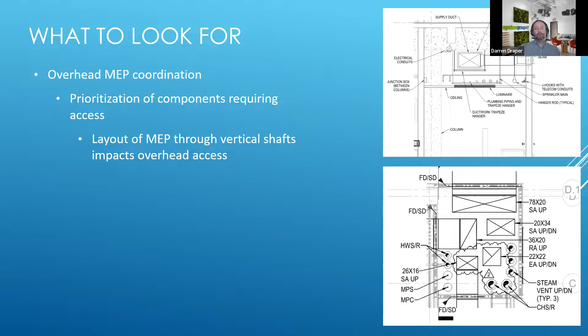More on maintenance access - you can see here a terminal unit with reheat at the bottom left. Something we really emphasize going into the BIM process is that contractors need to model the maintenance access, and generally speaking they try to do that. Code required clearances are 2 to 3 feet depending on what it is, so call it 3 feet out from the device. In this case, that controller needs about 3 feet of clearance in the horizontal.